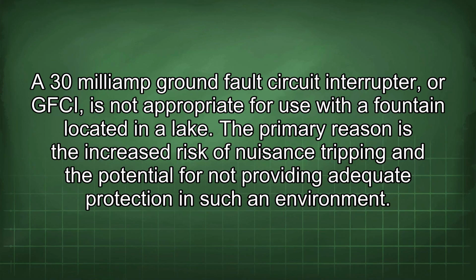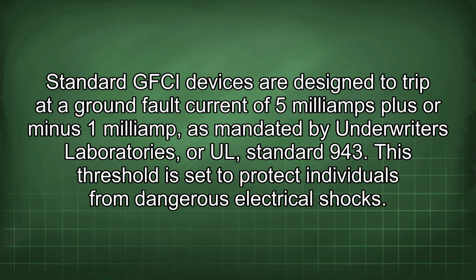A 30 milliamp ground fault circuit interrupter, or GFCI, is not appropriate for use with a fountain located in a lake. The primary reason is the increased risk of nuisance tripping and the potential for not providing adequate protection in such an environment. Standard GFCI devices are designed to trip at a ground fault current of 5 mA plus or minus 1 mA as mandated by Underwriters Laboratories, or UL, Standard 943. This threshold is set to protect individuals from dangerous electrical shocks.